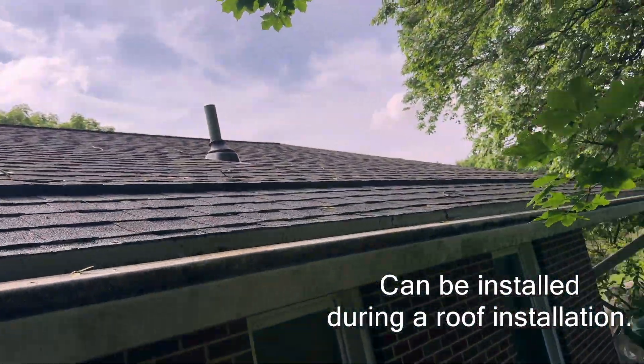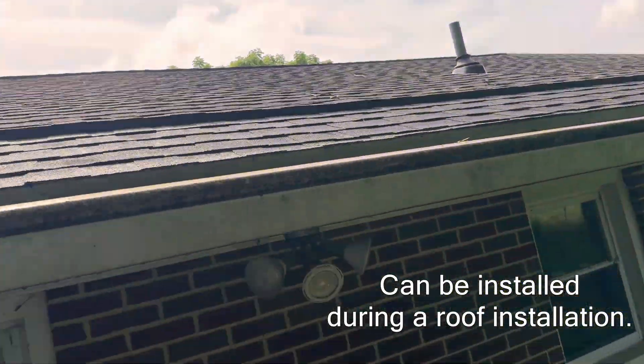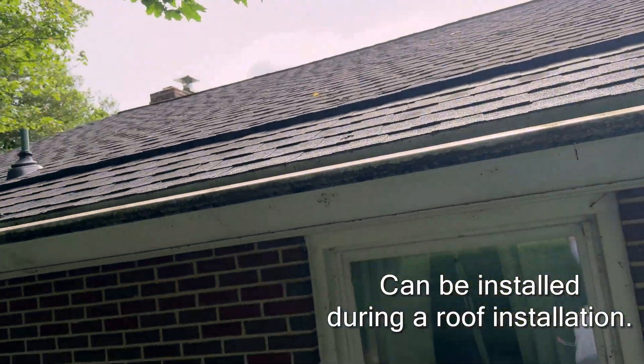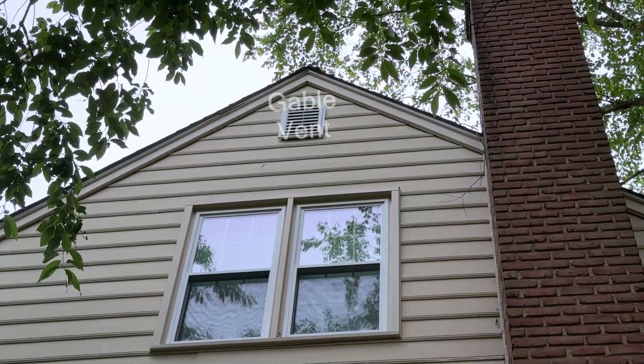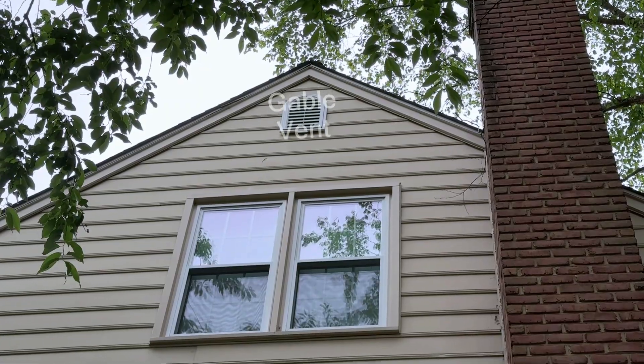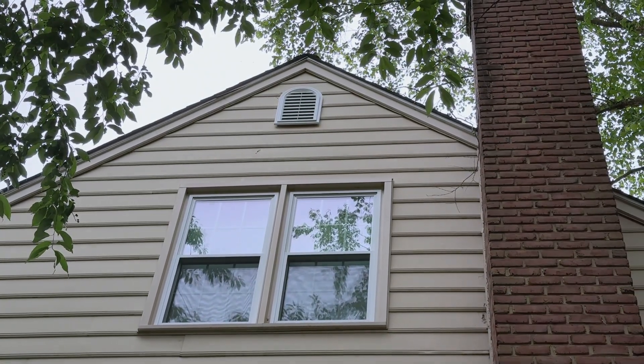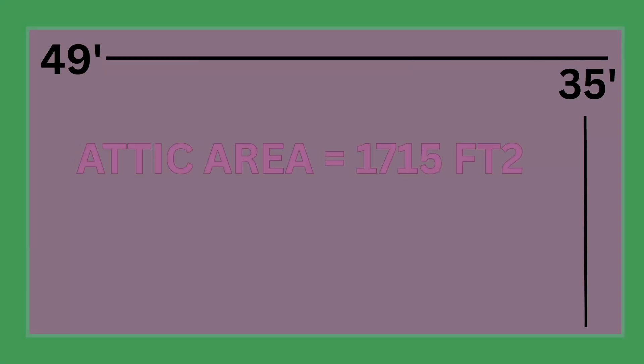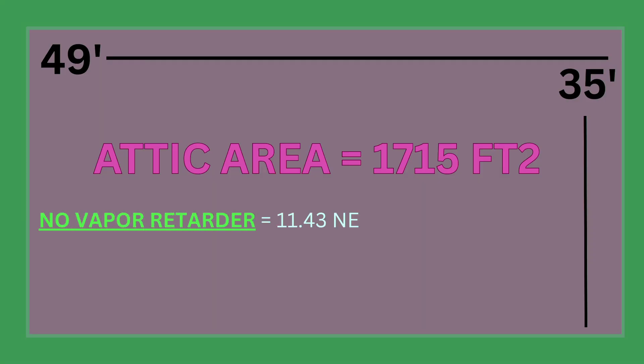But intake could also come from a special vent installed into the roof, like you see here. Usually houses that don't have an overhang are good candidates for this type of product. If you have gable vents, leave those out of your totals. If you get your net free airflow space nailed down, you can block them off to improve the airflow dynamics.